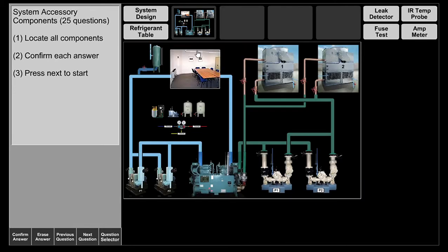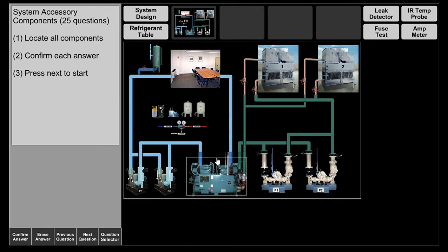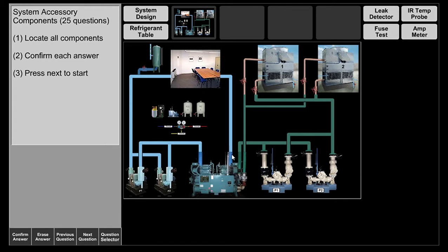Chilled water serves as the secondary refrigerant — the primary refrigerant is only inside the chiller. Chilled water comes out at 45 degrees, enters the room, and as it blows cool air it picks up heat. Utilizing the 10-degree rule, we now have 55-degree water, which increased 10 degrees due to the heat load in the room.